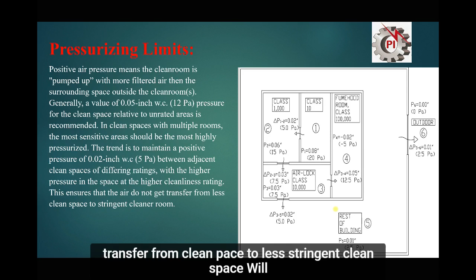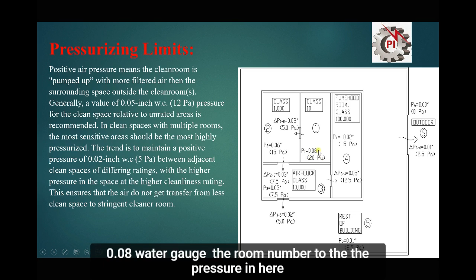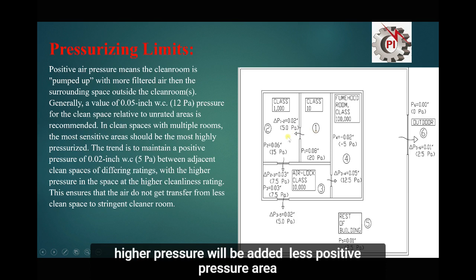If you see this diagram, we will start from here, room number 1, which is class 10. Here the pressure is 20 Pascal or 0.08 water gauge. In room number 2, the pressure is 15 Pascal. The difference between room number 1 and room number 2 is 5 Pascal. Because of this difference, the air from the higher positive pressure will enter the less positive pressure room. We will see how the air is moving.